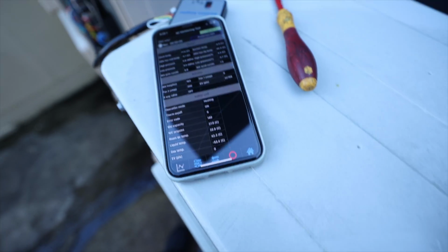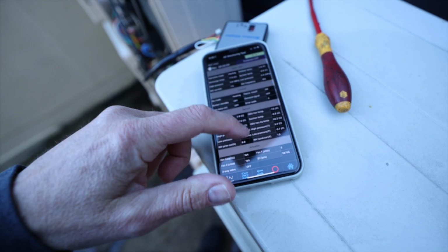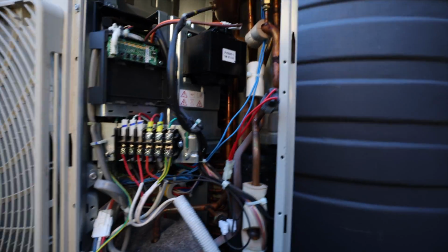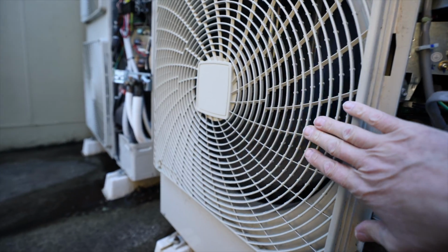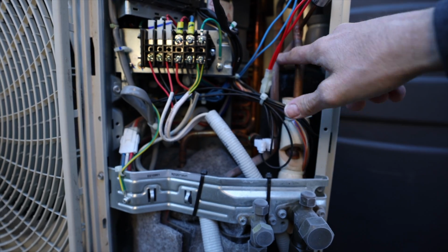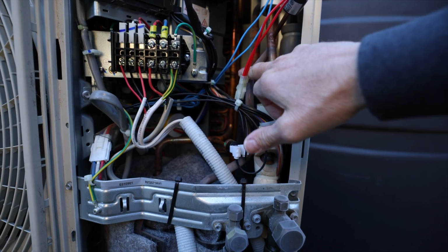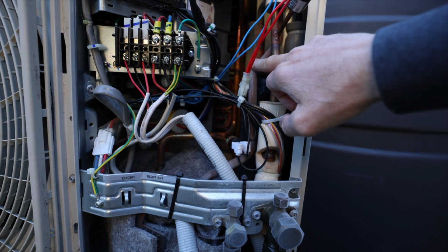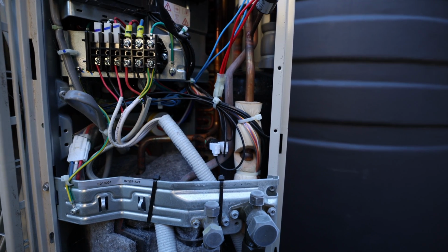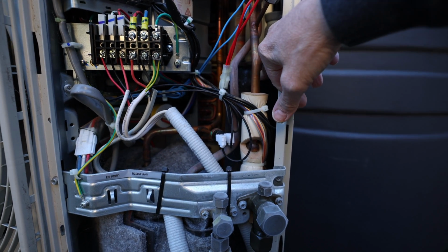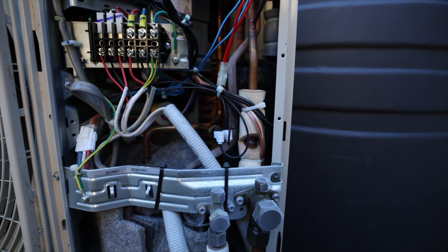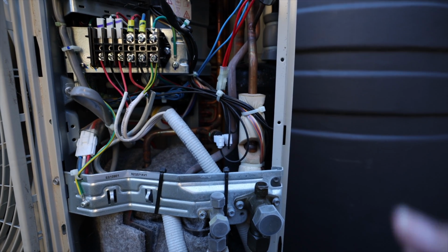Okay, so we weren't quick enough. It's already changed over back into heating. So we can see now that the outdoor fan's on. The refrigeration pipe, that's basically the pipe going to the outdoor unit and coil. And then this is the suction accumulator. So it's all starting to freeze over again, whereas before that had all defrosted.